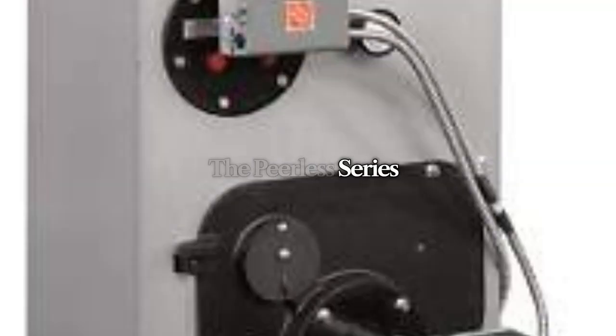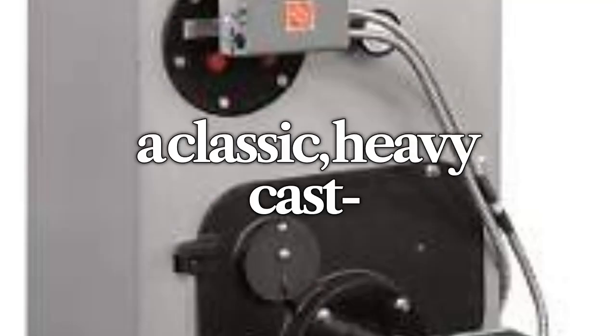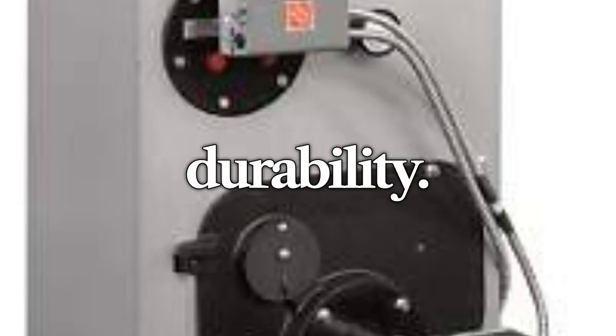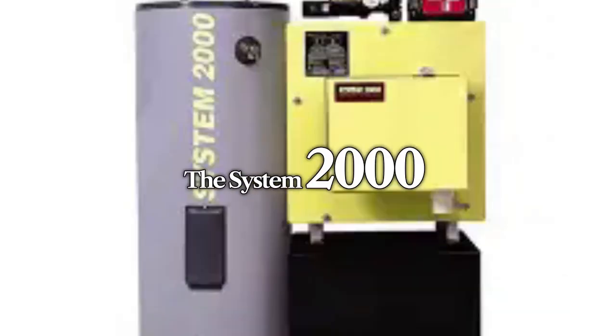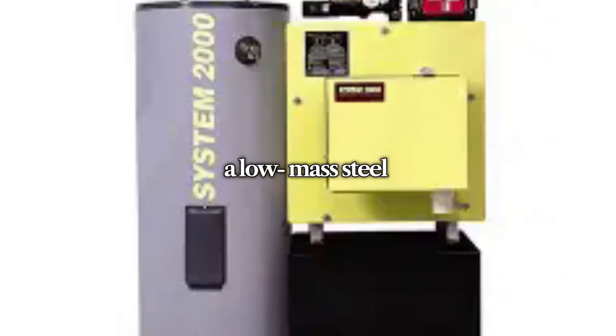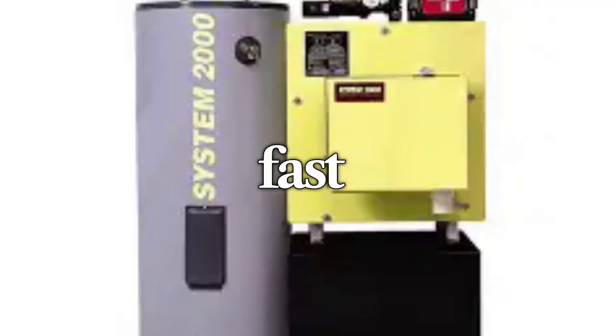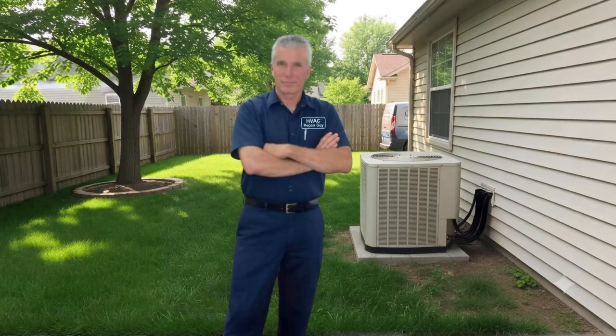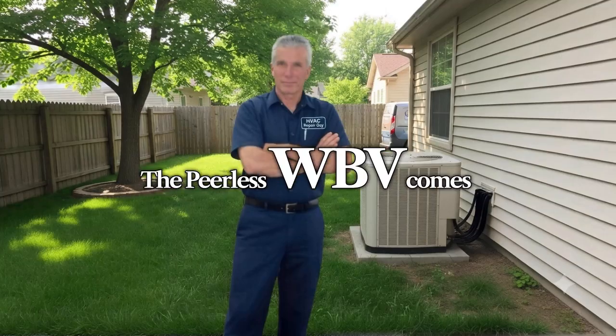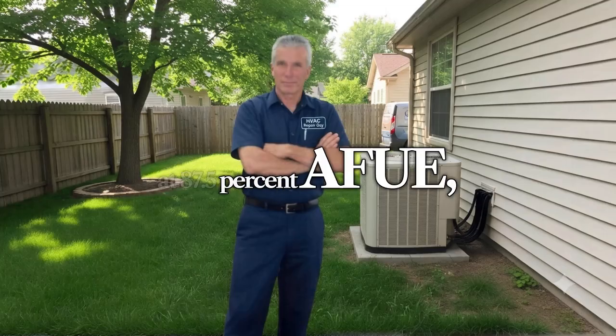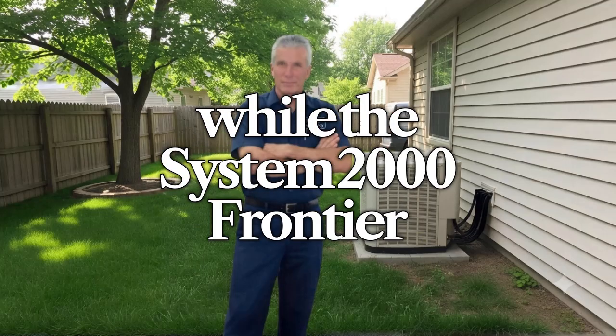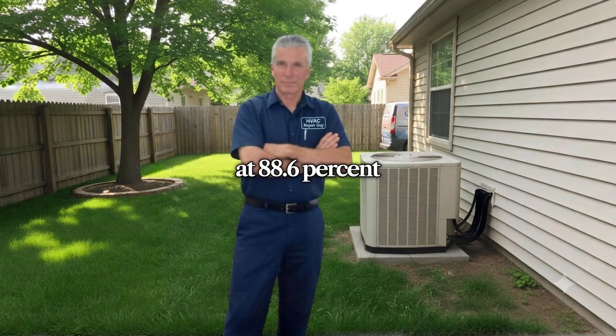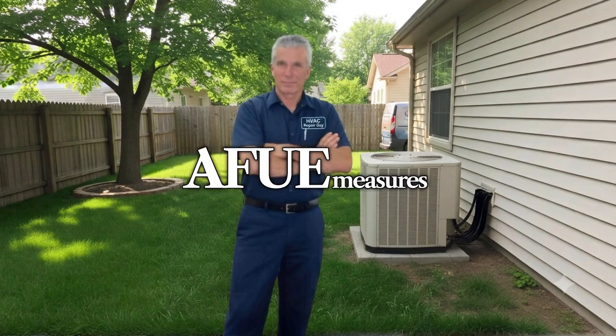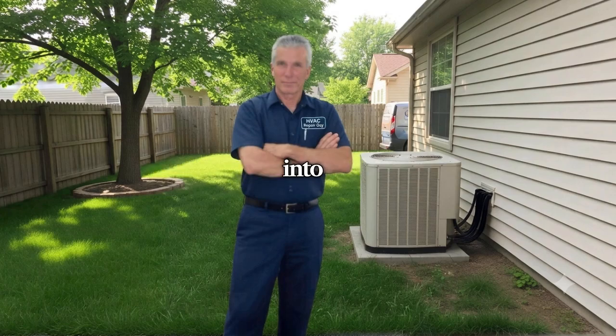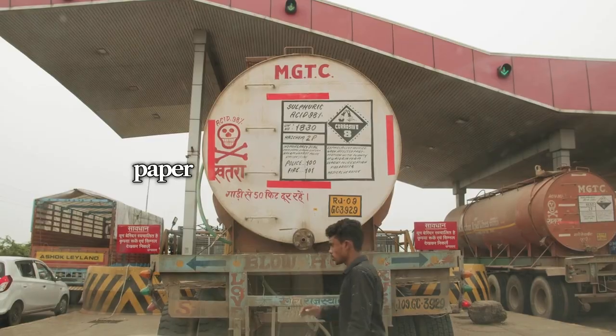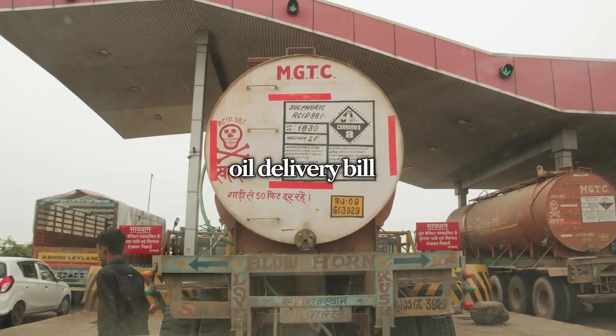The Peerless Series WBV is a classic, heavy, cast-iron boiler built for rugged durability. The System 2000 Frontier is a low-mass steel hybrid boiler engineered to heat up fast and minimize standby heat loss. Let's look at efficiency. The Peerless WBV comes in at 87.5% AFUE, while the System 2000 Frontier sits slightly higher at 88.6% AFUE. AFUE measures how effectively a boiler converts fuel into usable heat. A 1% difference on paper won't drastically change your oil delivery bill on its own.